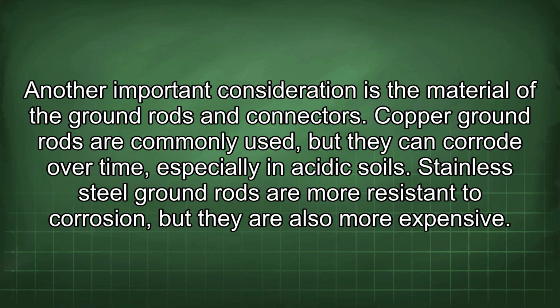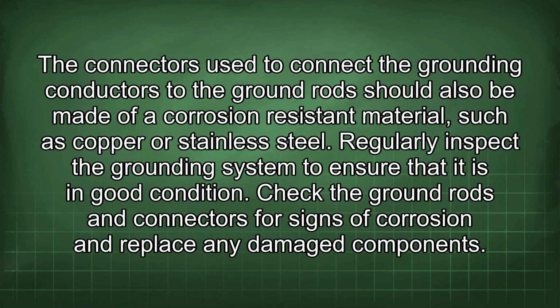Another important consideration is the material of the ground rods and connectors. Copper ground rods are commonly used, but they can corrode over time, especially in acidic soils. Stainless steel ground rods are more resistant to corrosion, but they are also more expensive. The connectors used to connect the grounding conductors to the ground rods should also be made of a corrosion-resistant material such as copper or stainless steel.